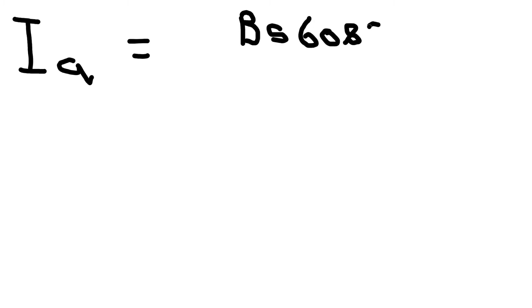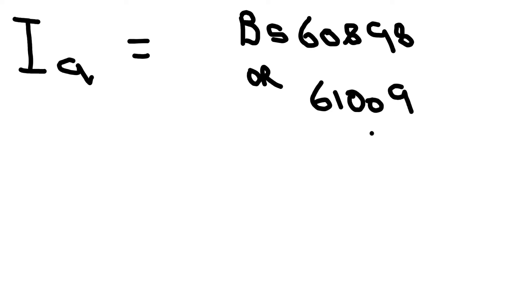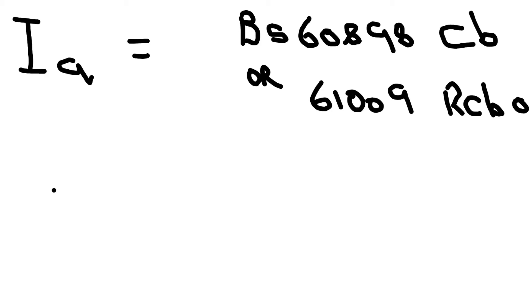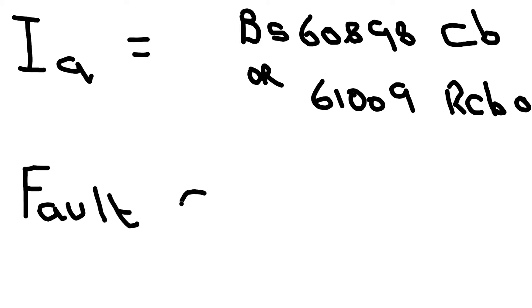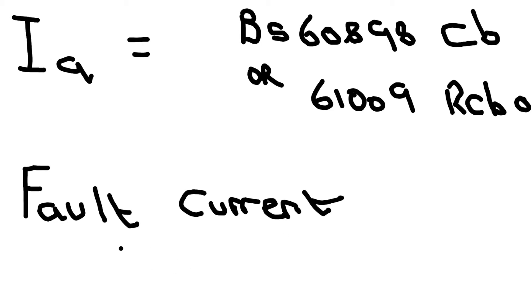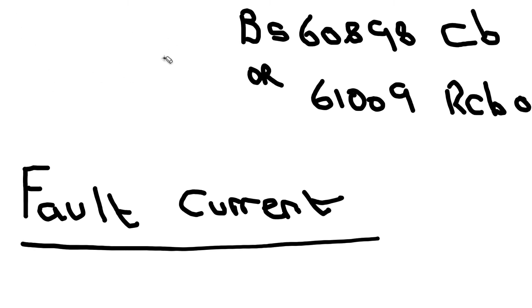There's another one which is I-A, and that is the current in amperes causing the automatic operation of the disconnecting device - in other words, the circuit breaker or RCBO within a specified time. A lot of this information you'll find in the wiring regulations and it can be quite confusing. The example I'm going to use today is from table 41.3.